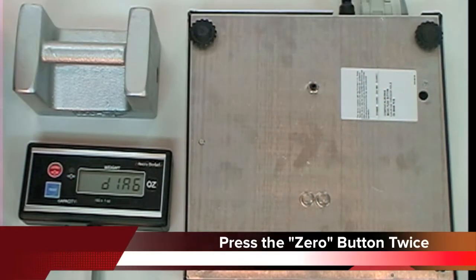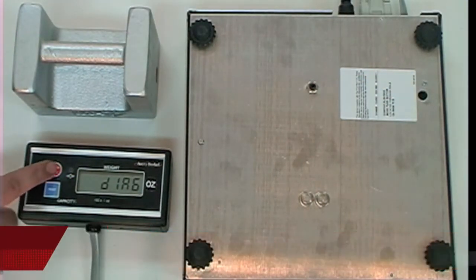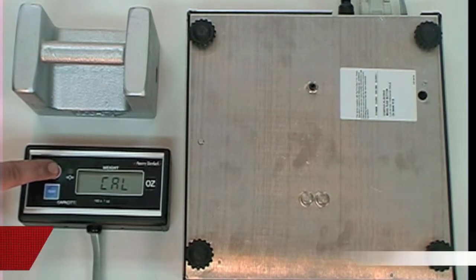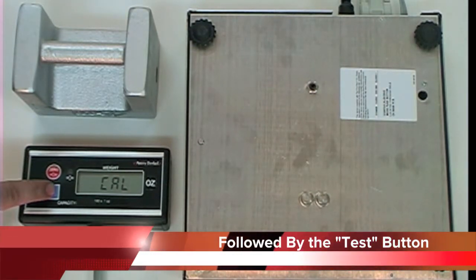Press the zero button two times so the display reads CAL for calibration, then select calibration by pressing the TEST button.